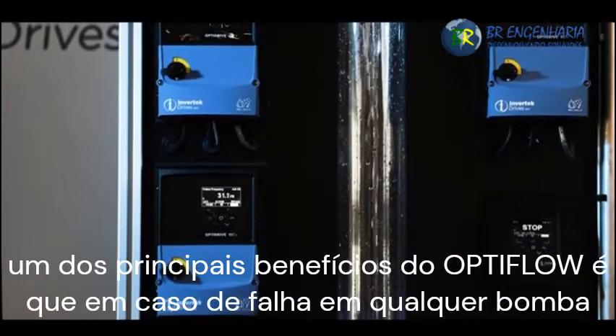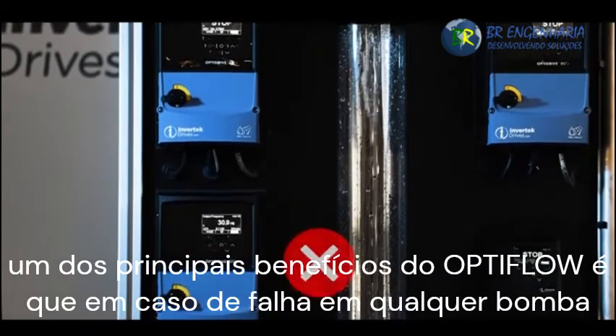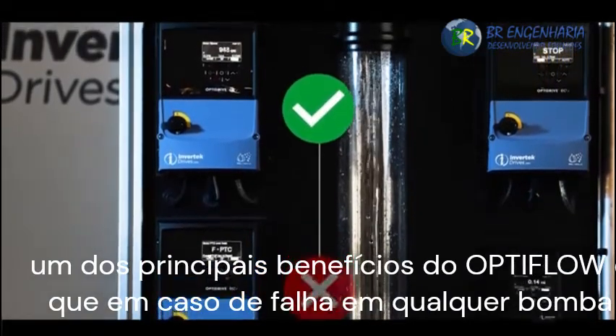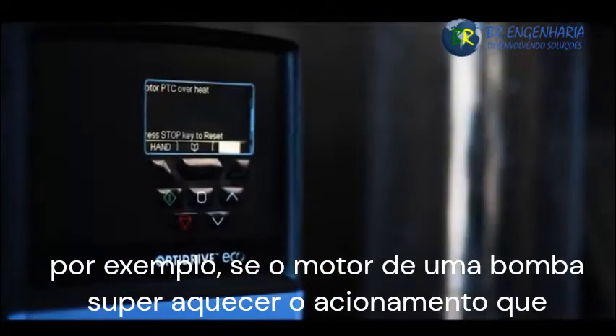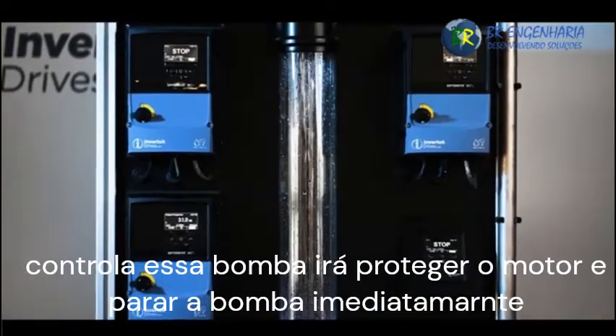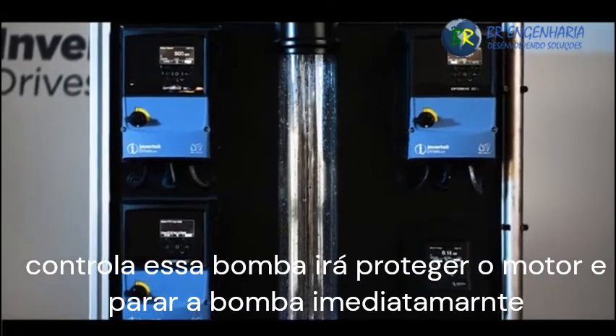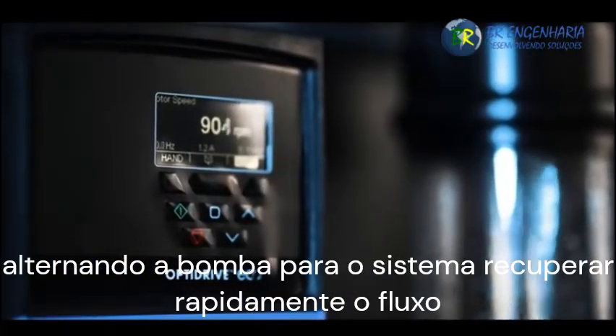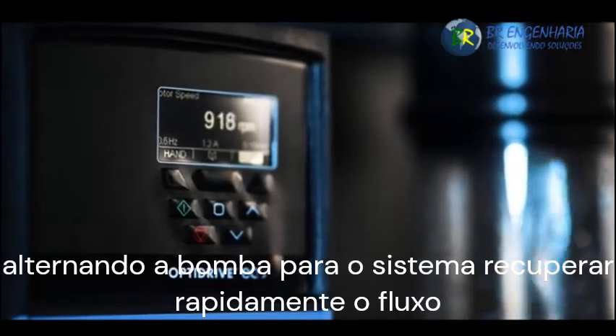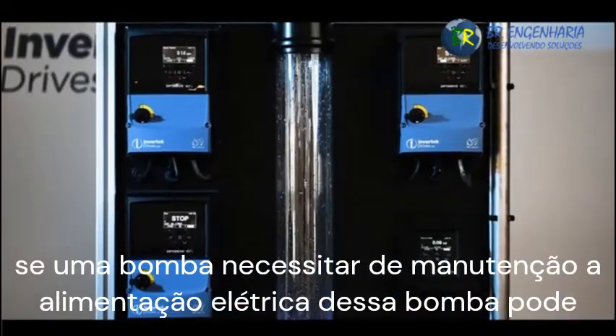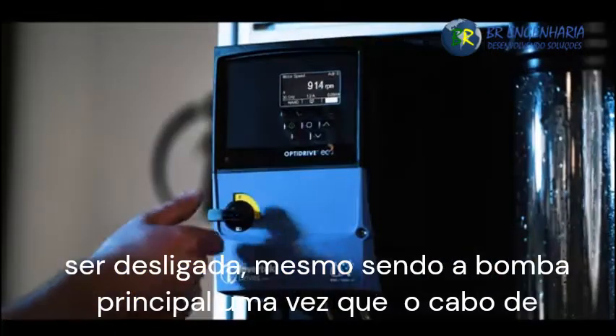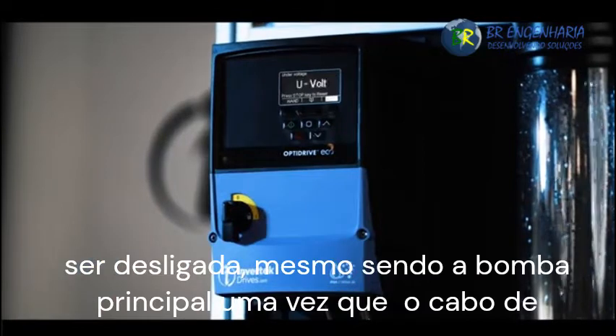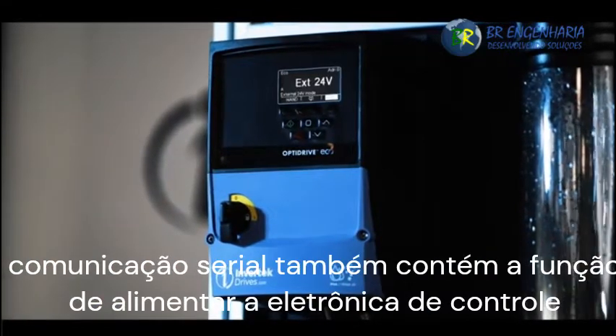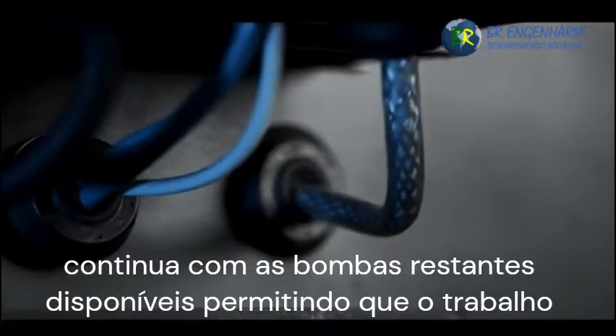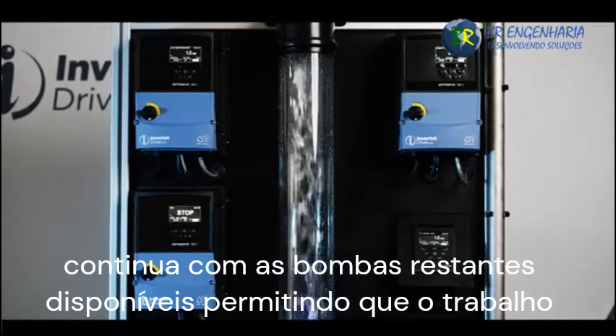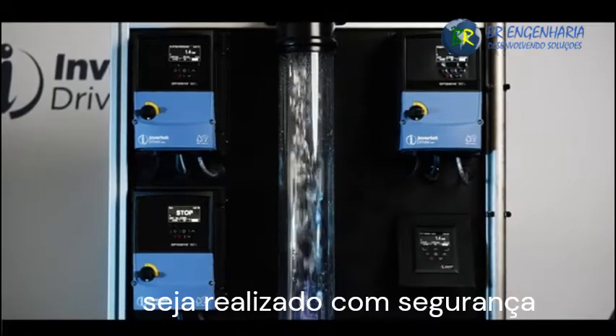A key benefit of the OPTIFLOW system is that in an event of a fault developing on any pump, an alternative pump will automatically start. For example, if one pump motor overheats, the drive controlling that pump will trip to protect the motor and stop the pump. Immediately, an alternative pump starts and the system quickly recovers, maintaining the flow. In the event that a pump requires maintenance, the electrical power supply to that pump can be isolated, even the pump connected to the master drive, as the serial communication cable also contains a control electronics power supply. Operation continues with the remaining available pumps, allowing work to be safely carried out.